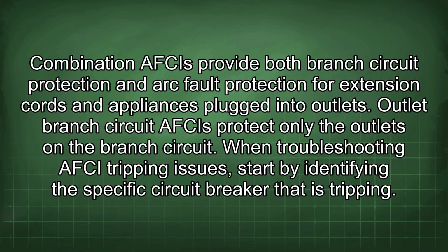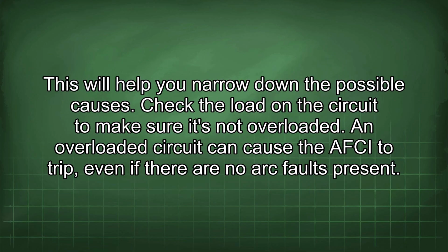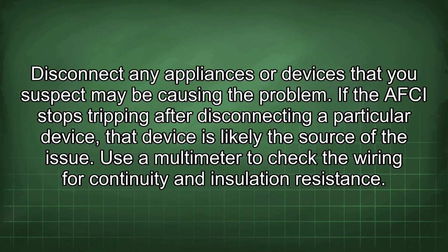When troubleshooting AFCI tripping issues, start by identifying the specific circuit breaker that is tripping. This will help you narrow down the possible causes. Check the load on the circuit to make sure it's not overloaded. An overloaded circuit can cause the AFCI to trip, even if there are no arc faults present. Disconnect any appliances or devices that you suspect may be causing the problem. If the AFCI stops tripping after disconnecting a particular device, the device is likely the source of the issue.